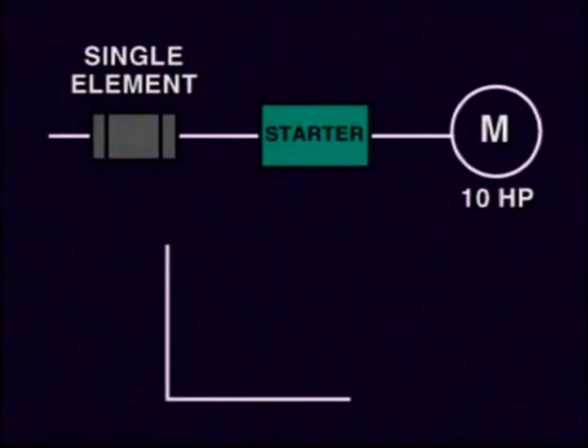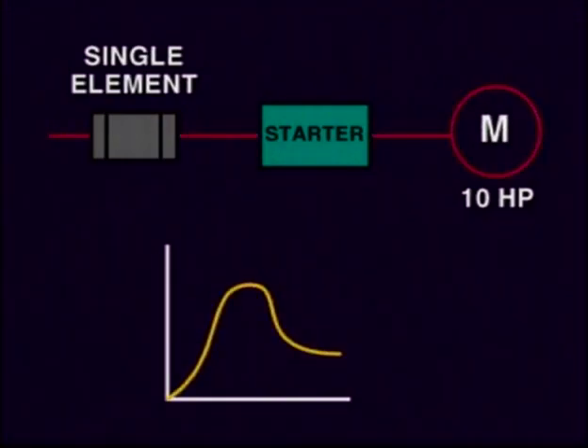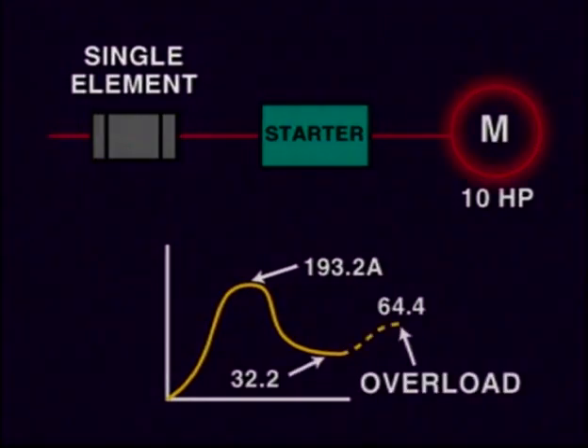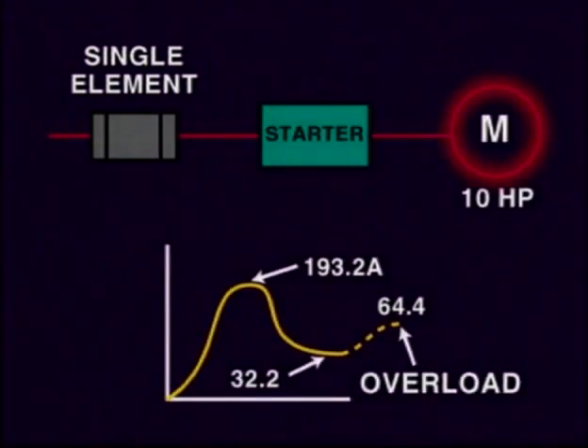This will happen because if a fuse is sized to protect a motor circuit, it will trip during the inrush current generated at the start. On the other hand, if the fuse is allowed to withstand the inrush current, it will not provide adequate protection when a motor is running at full load current. For example, if the 10-horsepower motor circuit is fused to the maximum inrush current of 193.2 amps, it runs the risk of being burned out if an overcurrent exists, at, let's say, double its full load current for a period of time. The single-element fuse must be sized higher than the full load current of a motor in a circuit to allow the motor to start. The proper sizing of non-delay time fuses is specified according to the National Electric Code.